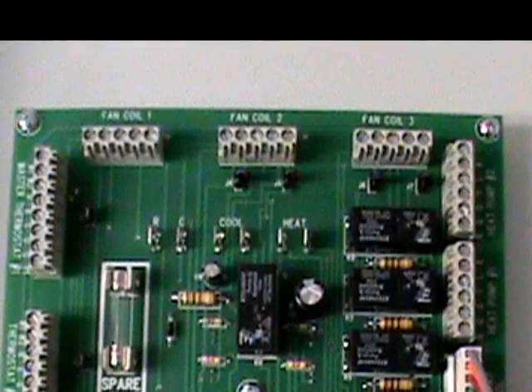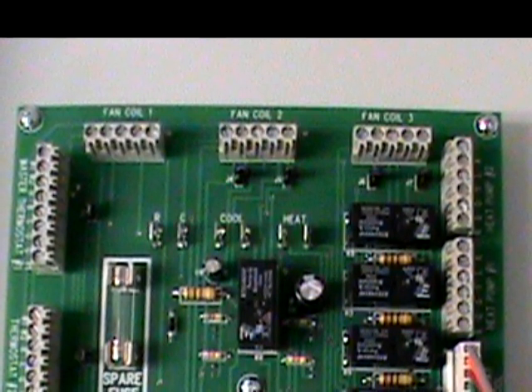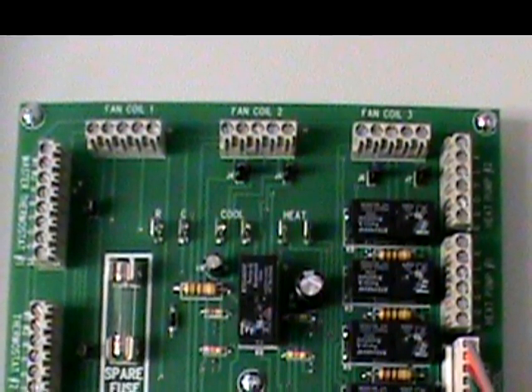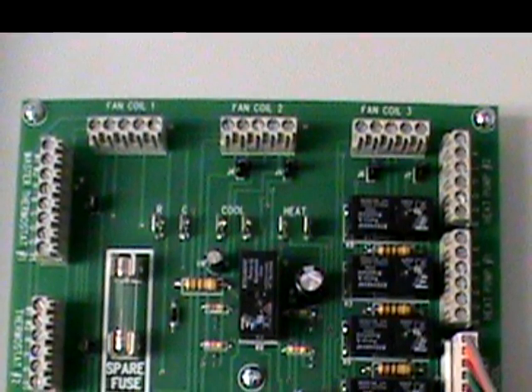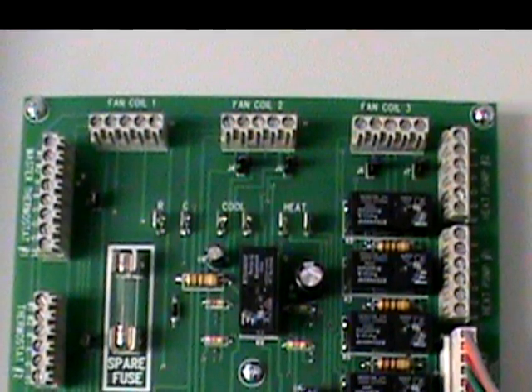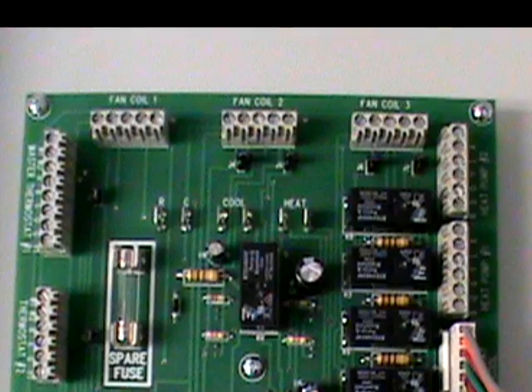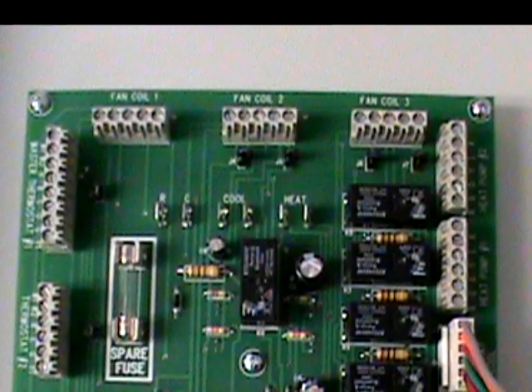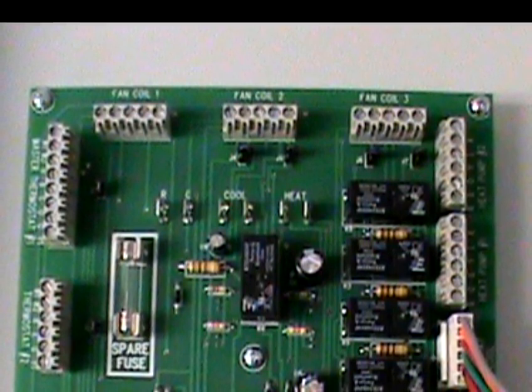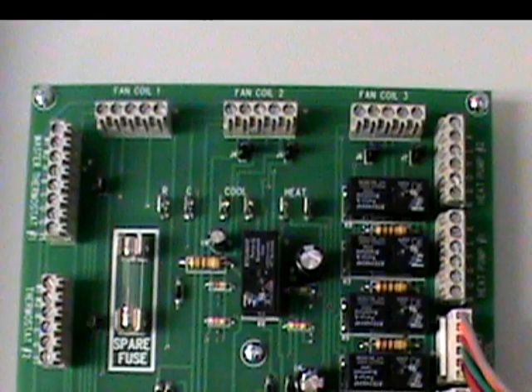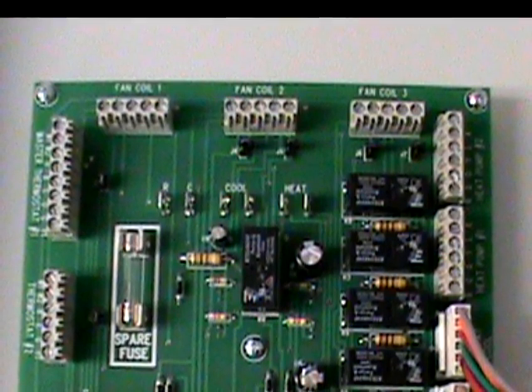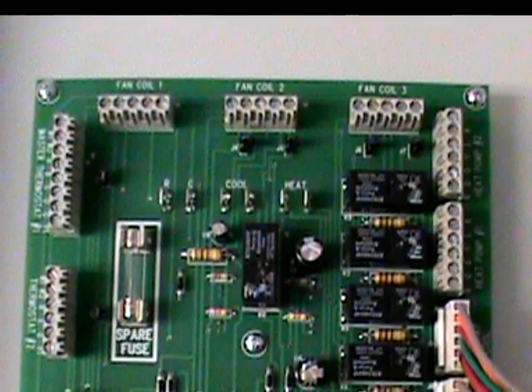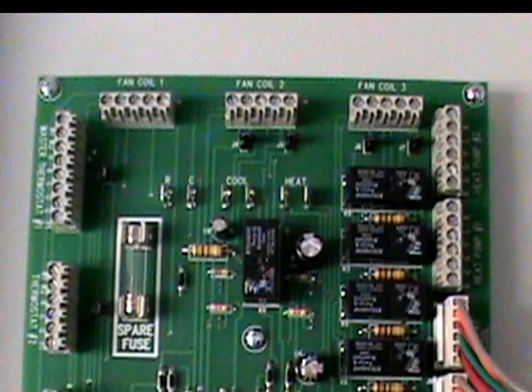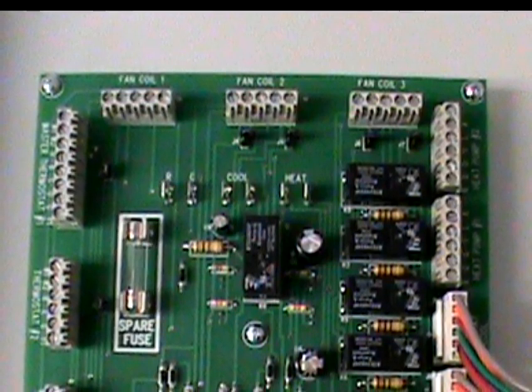Across the top of the circuit board are the individual terminal blocks for up to 3 fan coils, or 2 fan coils and 1 radiant floor zone, or 1 fan coil and 2 radiant floor zones. Typically, fan coils are used, but for dual fuel applications, furnaces can also be connected directly to the control module. A zone can have either ECM or PSC blowers controlled.